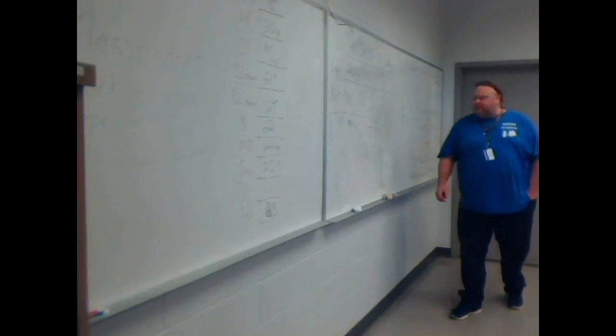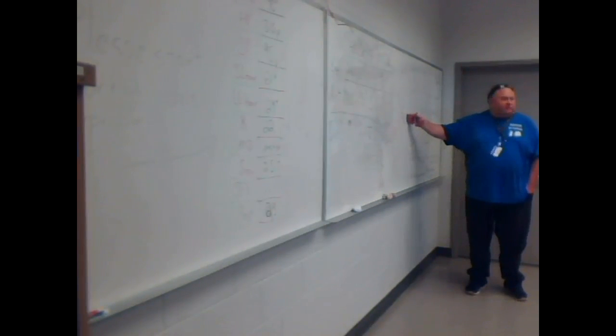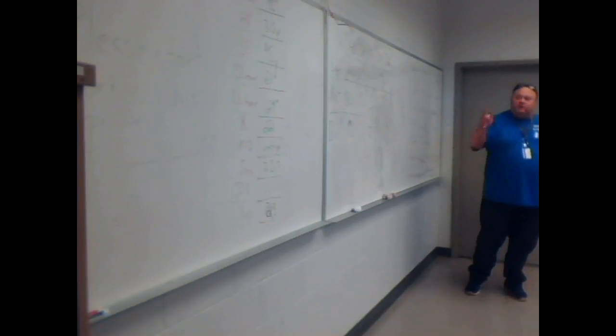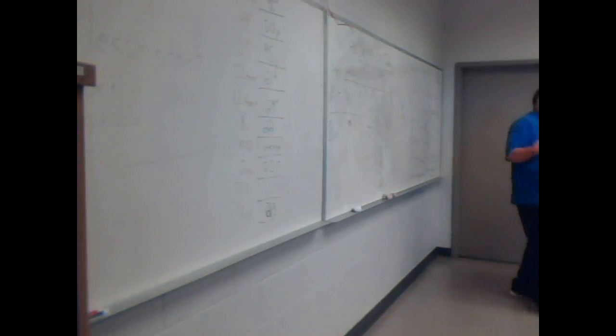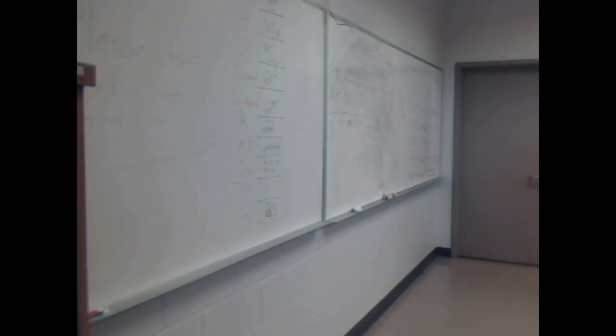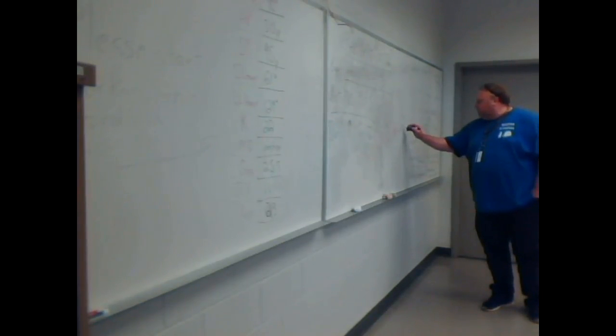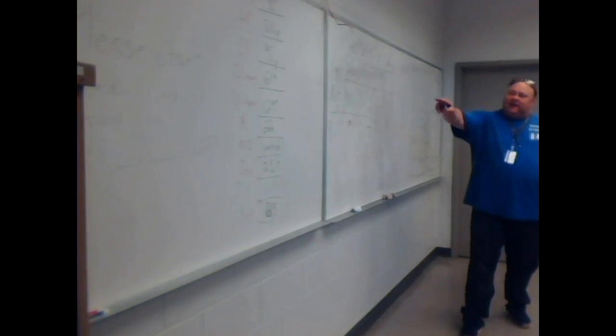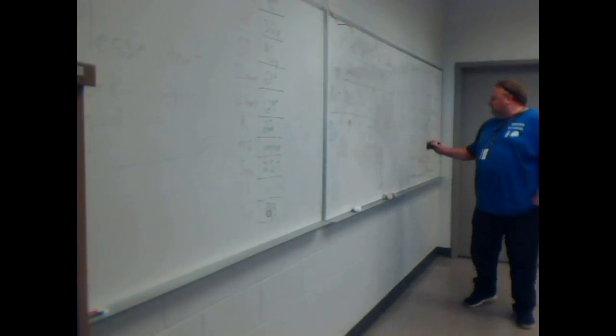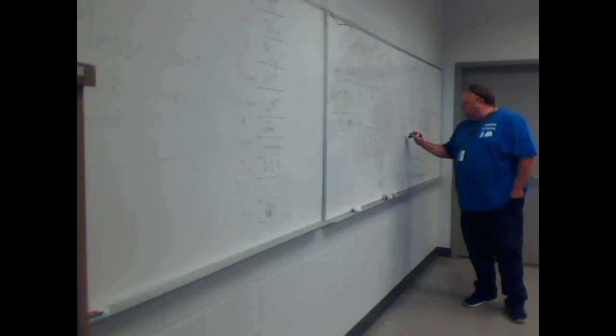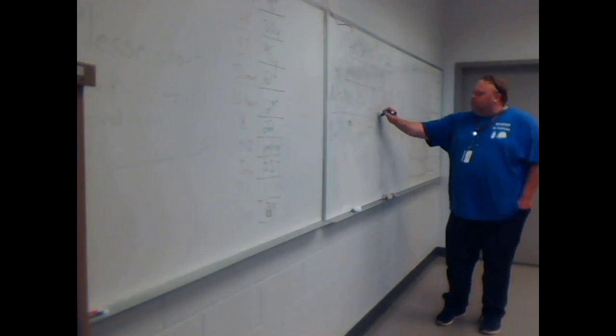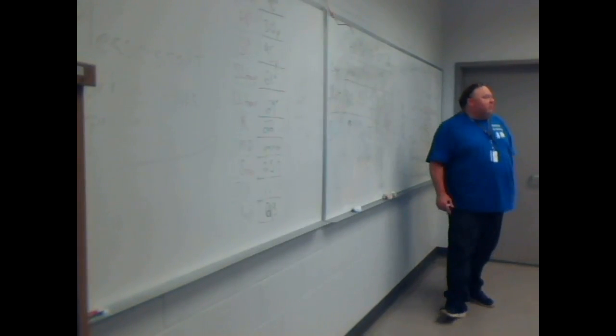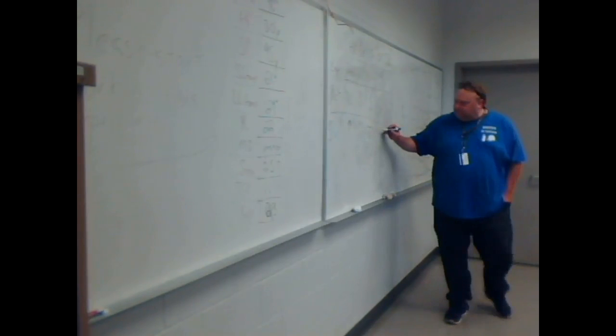And here, this is just the opposite. Instead of actual minus saturated, on subcooling it's saturated minus actual. So I start with 315 and convert that. 134, is that what y'all got? Yeah. 134 minus the actual liquid line temperature. That's 5? Okay. Now, is 5 above or below what we're expecting? Below.